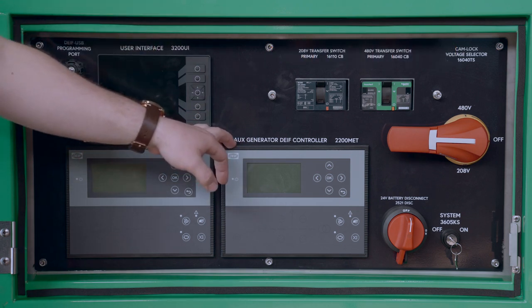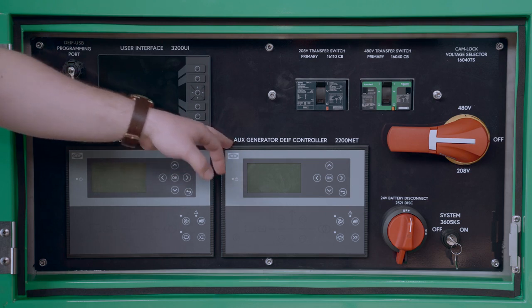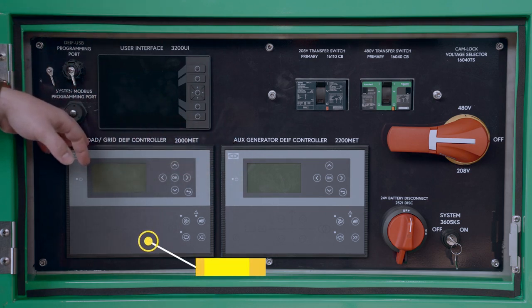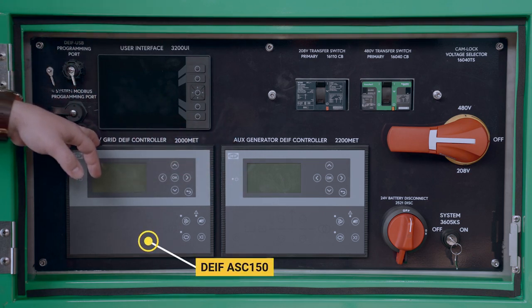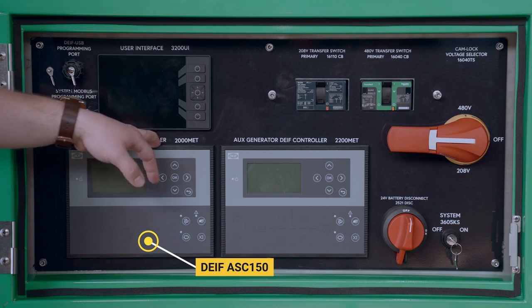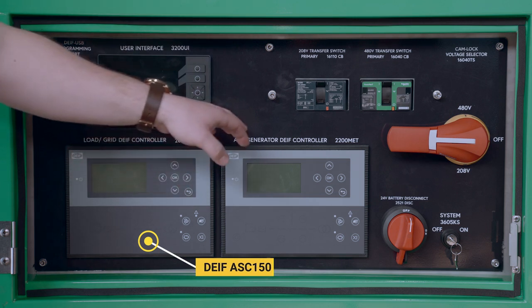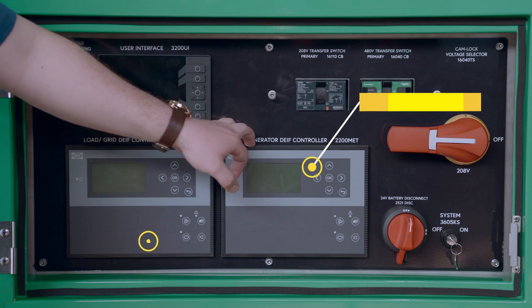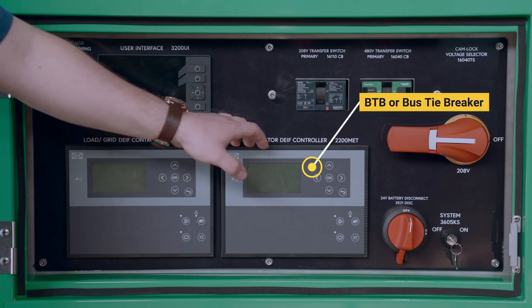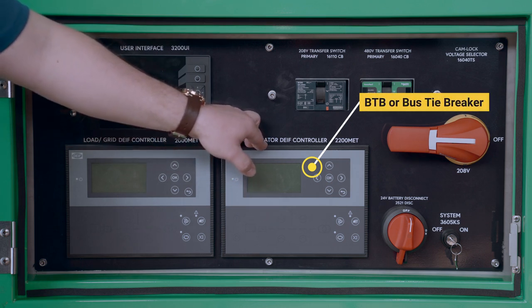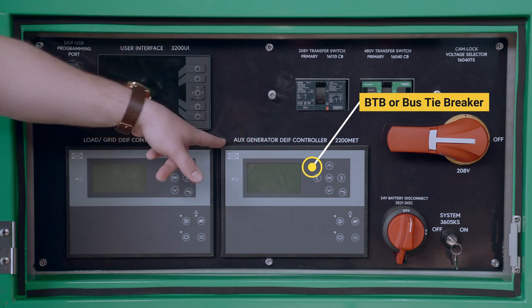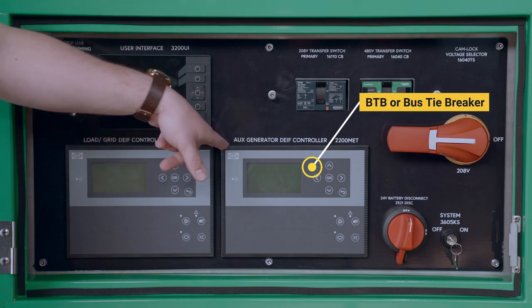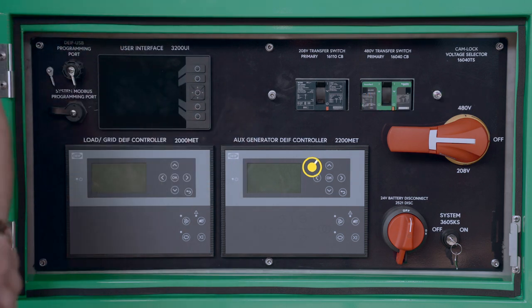Also in the front, we have two dual DEIF control units. The first DEIF is set up as an ASC150 energy storage unit, which is set up for paralleling with other paralleling units. Second is our DEIF BTB, or bus tie breaker, which is used to synchronize with non-synchronous generators. Each DEIF unit is equipped with 6 voltage transformers and 3 current transformers to measure the power, current, voltage, and frequency of the power going through the device.